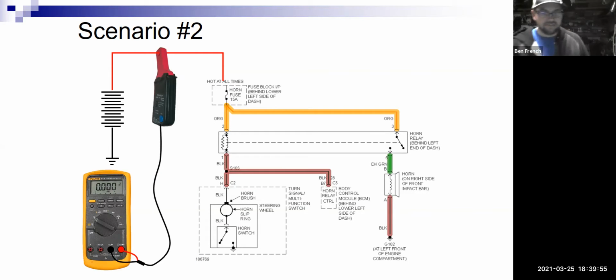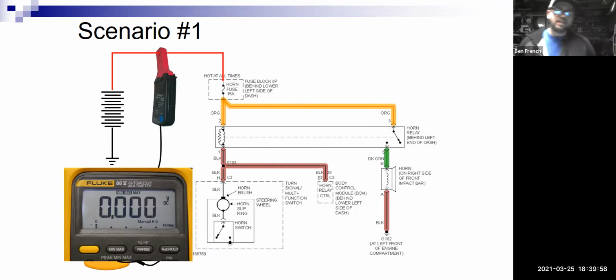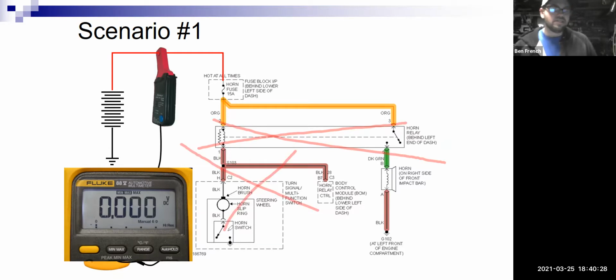We push on the button and get no amps flowing at all. That tells you something, right? Maybe the relay is unplugged, or totally defective, or there's no path to ground right here — but I have absolutely nothing flowing. So if I had no amps flowing at all, I'm looking at the relay, maybe this fuse is blown. I'm looking right here if I get past the relay, but have no current flowing at all.